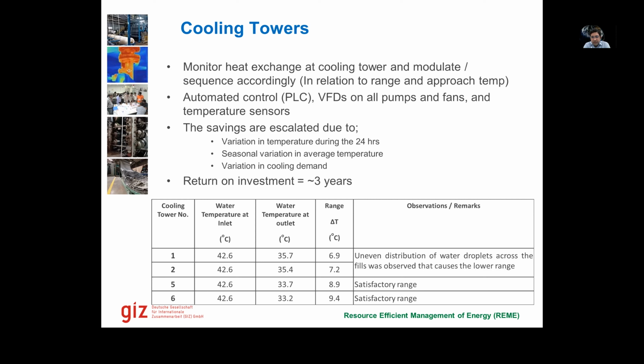And we saw that in number 1 and number 2, the cooling tower fills were clogged, and the distribution of the water droplets that are falling was also not even. That was causing the low range. So we got these cooling towers fixed, did some maintenance, and they started working pretty fine.